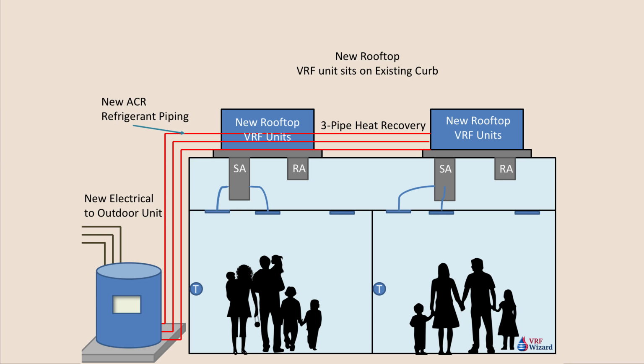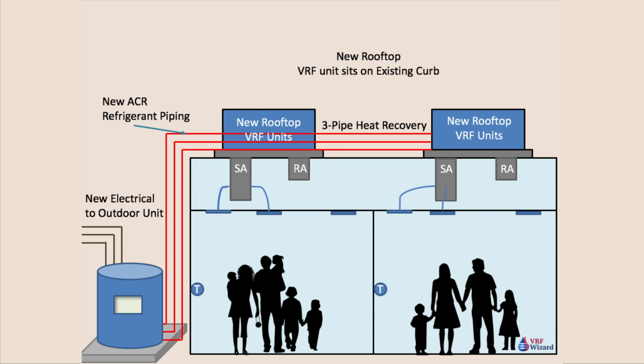minimum volumes. So to summarize, you use these new VRF package rooftop units to replace existing DX package units; currently they're only doing 3 to 5 ton. So in the future I'm sure they'll expand the line to include larger units, and then you need at least a minimum of replacing 6 tons. That's basically the smallest VRF outdoor unit you're going to get. So you need to replace at least 2 3-ton units or some combination of units that amounts to 6 tons or more. So this replaces existing old 3 to 5 ton rooftop package units, curb mounted.